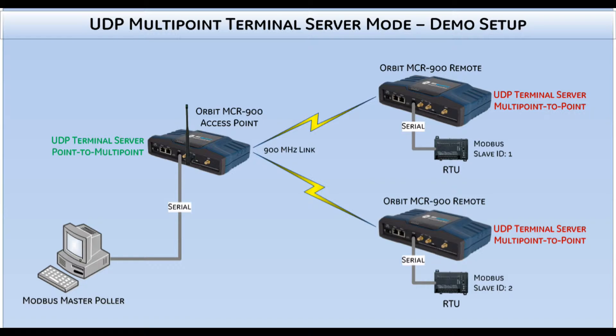The packet will reach both Orbit remotes because they will be configured in multipoint mode. Depending on the slave ID that the Modbus master requests, only one of the RTUs will respond. Once the RTU responds, serial data will now be present on the Orbit remote COM1 port, where it will create a new UDP packet and send it to the point device configured in the terminal server. This point device will be the access point. Now that we have a plan, let's configure the system.